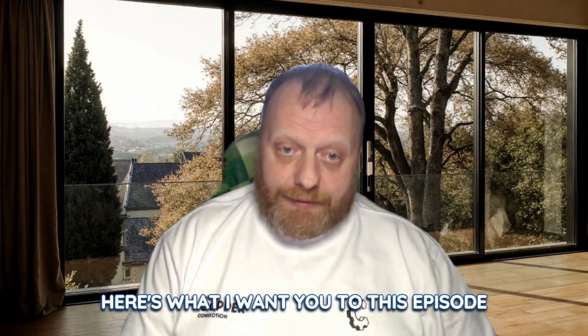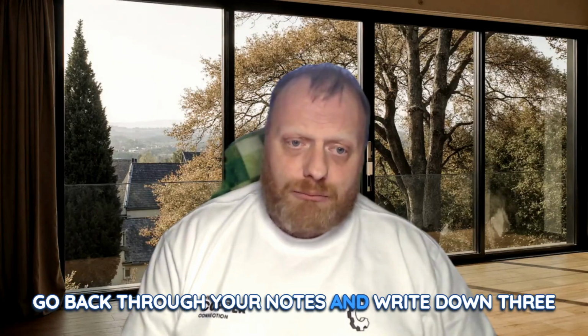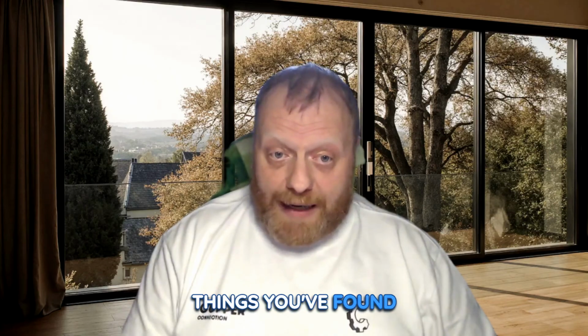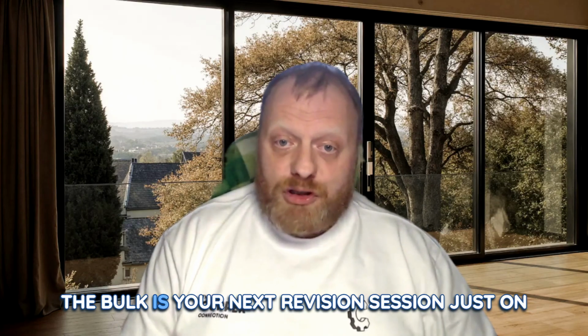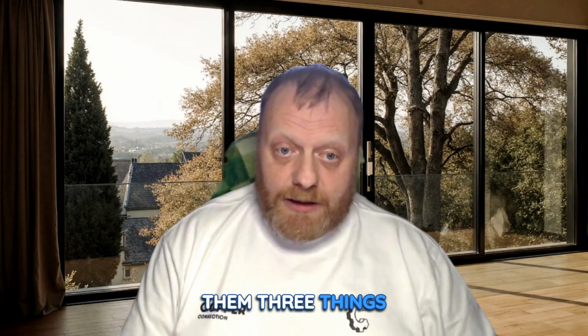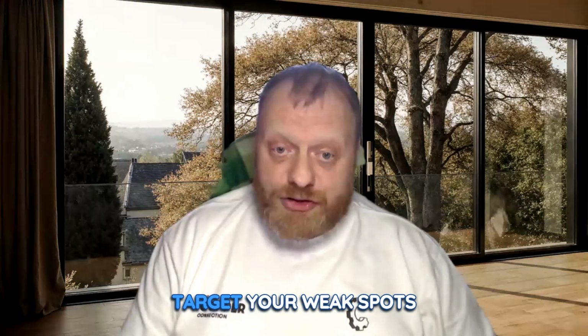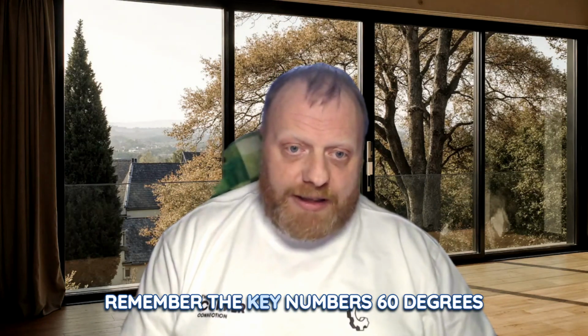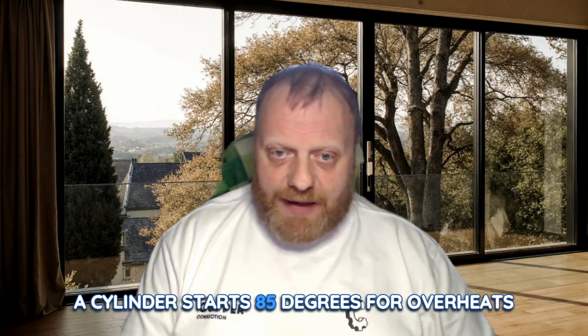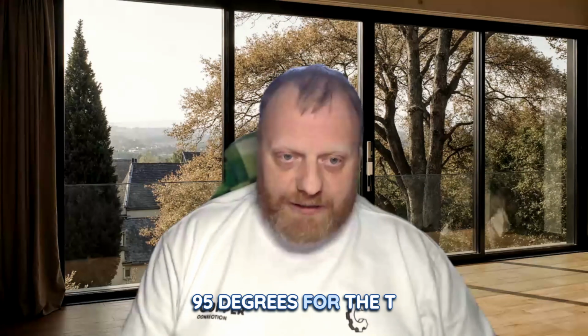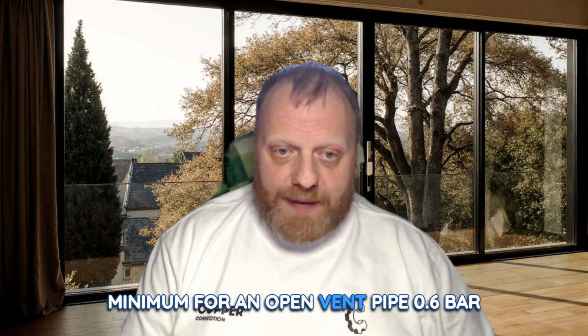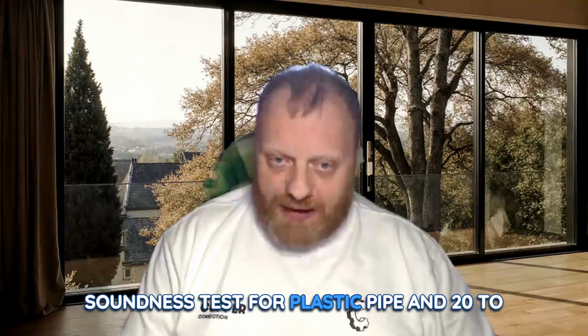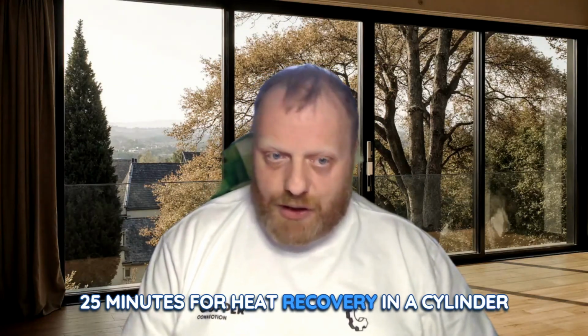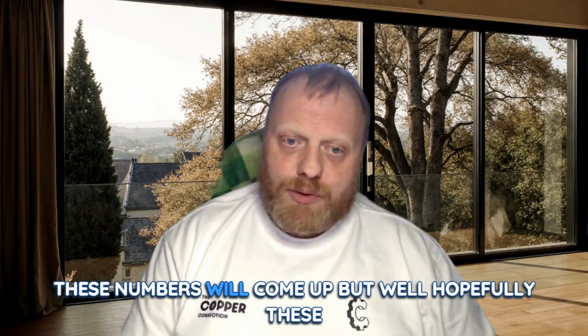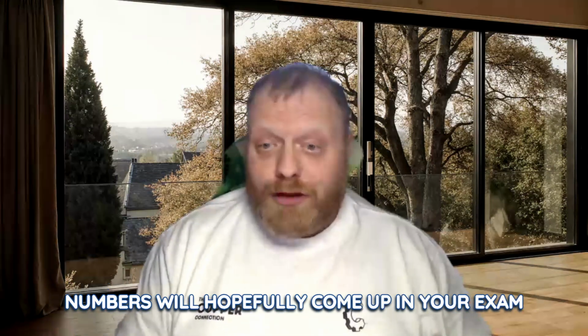Here's what I want you to do after this episode. Go back through your notes and write down 3 things you found hardest to remember. Then focus your next revision session just on those 3 things. Don't try and revise everything at once. Target your weak spots. Remember the key numbers: 60 degrees for cylinder starts, 85 degrees for overheats, 95 degrees for the TMVs, 19mm minimum for an open vent pipe, 0.6 bar soundness test for plastic pipe, and 20 to 25 minutes for heat recovery in a cylinder. These numbers will hopefully come up in your exam.